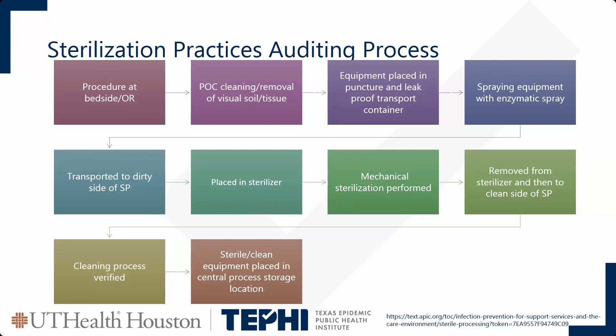You're watching them put in the chemical indicator specifically in the pack, and then you're watching them load it. And then in this area you are also checking logs for temperature, air pressure, and humidity. Those are big requirements as well, to make sure that we're ensuring the right practices and that everything is within compliance, and that you're not overweighting the trays. They should only be 25 pounds because 25 pounds has been seen as a weight someone can hold freely away from their body, and they're not bringing it towards their body and therefore cross-contaminating it because it's touching their scrubs. So then you put it in the sterilizer, and you should have a chemical and biological indicator, and then once that pass is run, you take it out and it's put on the clean side, or now the sterile side, with all the other equipment, and then you're verifying your logbooks at this time to ensure that all practices have been met and quality standards.